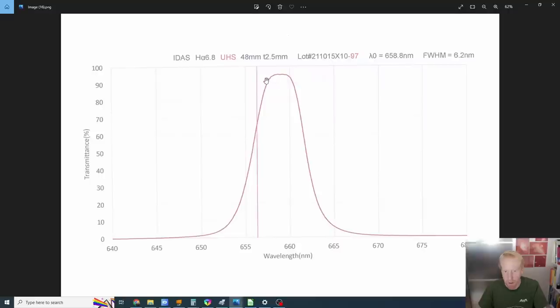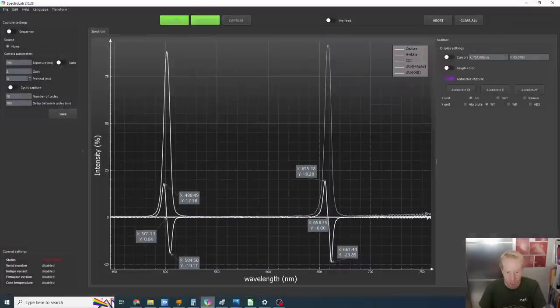That means that when I do my spectrometer tests, I will be measuring everything and comparing everything. I'll be looking at the center of the flat top, I'll be looking at this lambda zero, I'll be looking at the full width half max, and I'll also be looking at the left part - like the left point of the full width half max and the right point of the full width half max - so we can compare all of that. Now, I don't have the Excel data of the filter, just that printout, so I had to kind of play it by ear and sometimes evaluate what the figure would be. But enough to be able to compare the official lab spectrometer measurement to my own measurement.